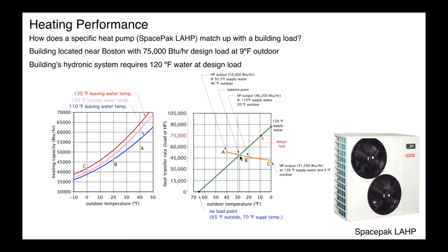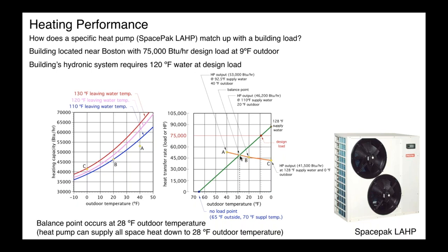Well, the heat output from the heat pump continues to go down. It is lower than the building load, and some other supplemental system is adding that additional heat. So the heat pump doesn't shut off at 28. This heat pump can operate well below zero. It's simply making a lower and lower contribution to the total. And again, we can factor that into our model.